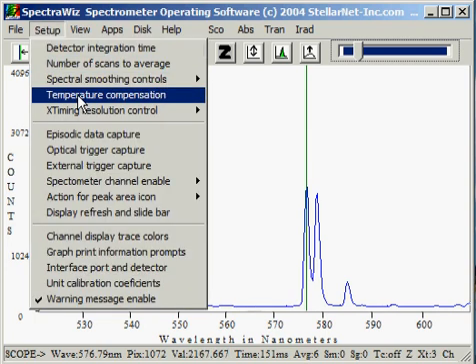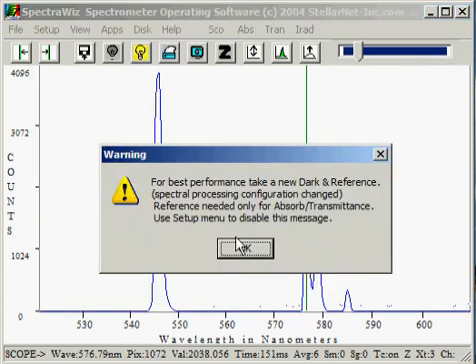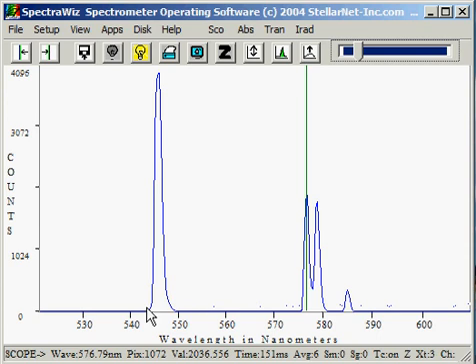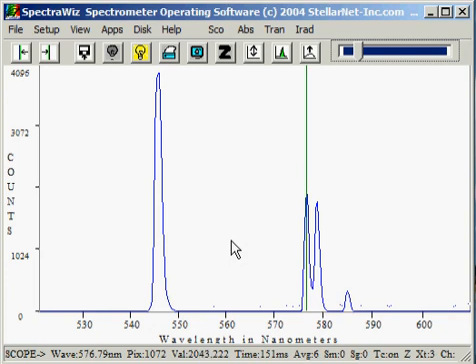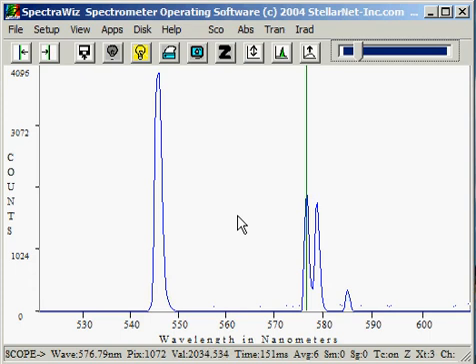Temperature compensation is currently turned off. I'm going to turn it on to show you the effect — the baseline is clamped at zero. This feature is updated every 15 seconds based on the temperature reading from the detector. This allows us to keep the baseline extremely stable when the external temperature changes up or down, locking it into a solid baseline.